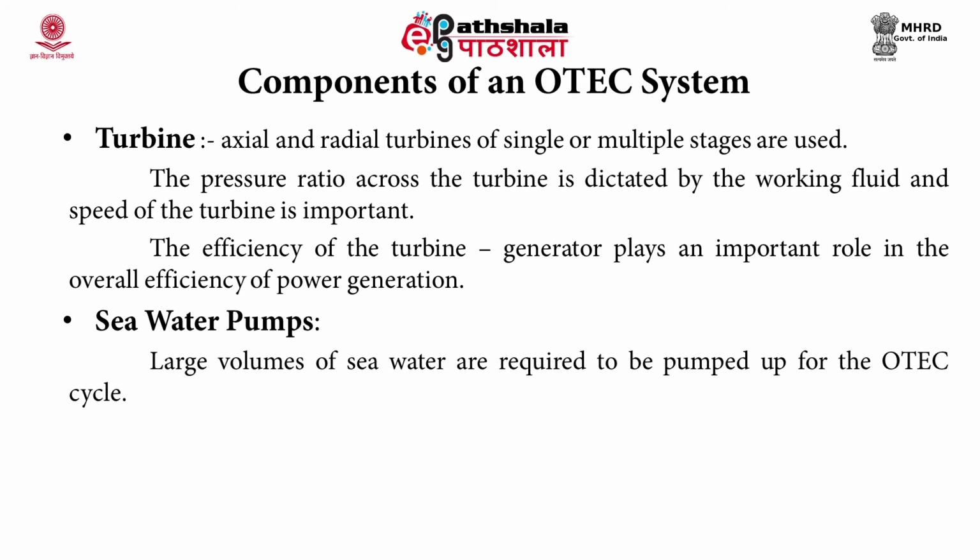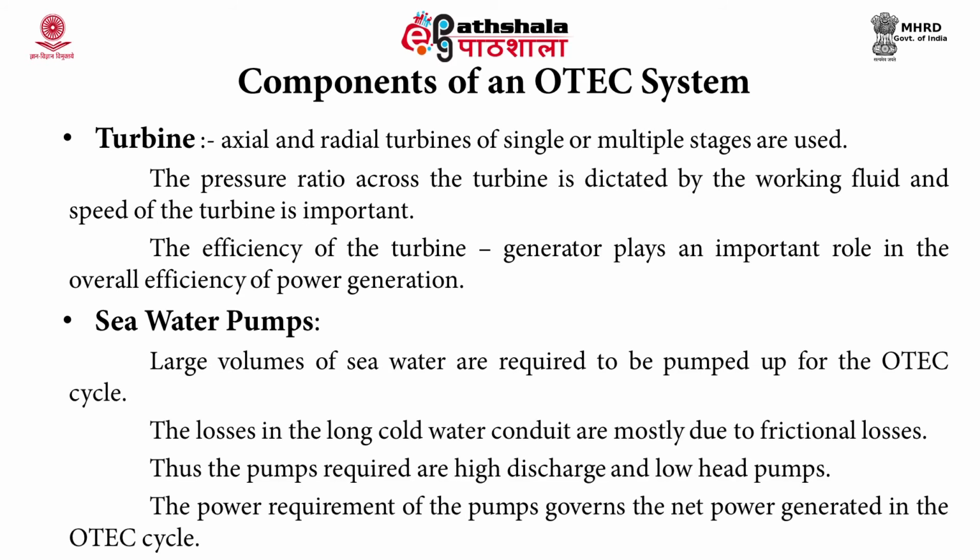Seawater pumps. Large volumes of seawater are required to be pumped up for the OTEC cycle. Generally, the losses, especially in the long cold water conduit, are mostly due to frictional losses. Thus, the pumps required are high discharge and low head pumps. The power requirement of the pumps governs the net power generated in the OTEC cycle.